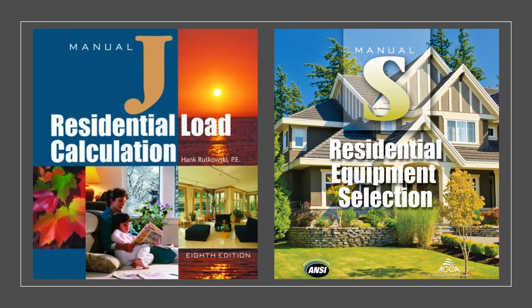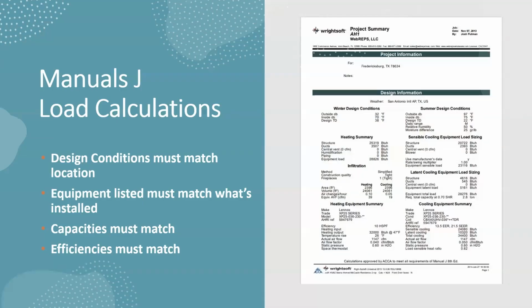If you're not familiar with what those things do: manual J shows load calculations, the heat coming in and leaving a building at any particular time, annually. What are the BTUs needed to either heat or cool to offset the heat coming into the building? So the design conditions must match the location.